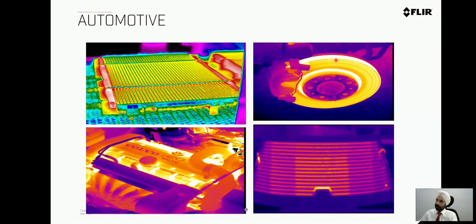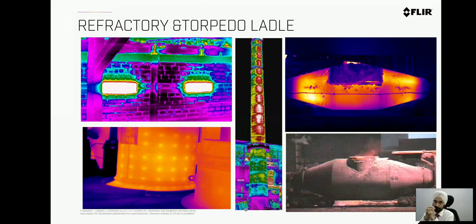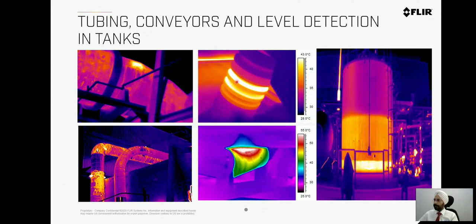In the steel industry, a steel ladle with molten steel at 1,134 degrees centigrade requires good insulation. If insulation fails, the consequences are very critical. A thermal camera is very handy here — you can clearly see if insulation is getting problematic, potentially increasing ladle turns and saving significant costs. Refractories and chimneys with improper insulation can also be easily identified. Additionally, friction events and oil level detection in tanks are possible because emissivity differs where liquid is present — tank level detection is possible with correct sensitivity and emissivity settings.